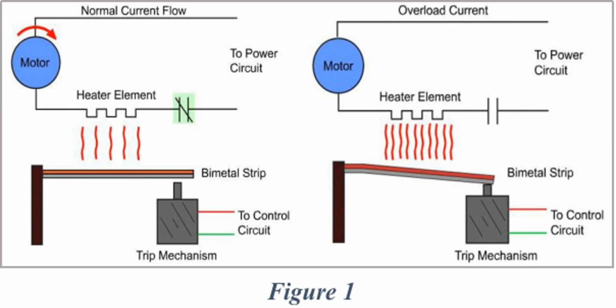The causes of overload tripping. The tripping of thermal overload relay happens due to following reasons. Overload current. Too low threshold value. Short circuit fault in a motor circuit. Poor quality of the relay. The magnetic overload relay has almost the same tripping causes as mentioned above. Advantages and disadvantages. There are some following noticeable advantages and disadvantages of both types of overload relays.